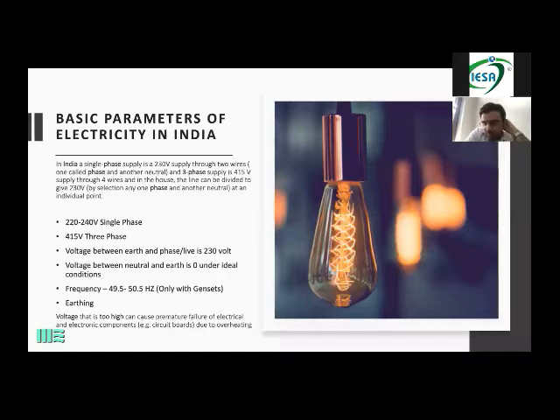So again, when we say single phase has to be 220 to 240, if you have a multimeter on site, or your distribution boards are equipped with a meter, whenever you put a multimeter on the black and any of the colors, red, yellow, or blue, you will always get 220 to 240 volts only. When you check color to color, that could be any combination, red to blue, blue to yellow, you will always get 415. Once those 2 parameters you see on a multimeter, your electricity is good to go.